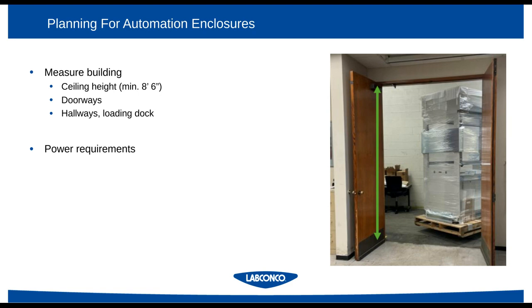Also, power is really important, both understanding the power requirements for your automation instrumentation and also for the enclosure itself. Oftentimes, the larger the enclosure, the more energy required, and while not insurmountable, it does take careful planning, as oftentimes a typical 115 outlet for a small instrument may not be sufficient.